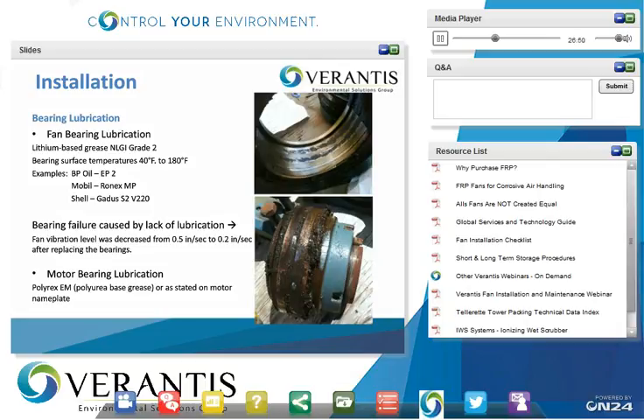Bearing failure caused by lack of lubrication. The arrow is pointing to the bearing housing and the bearing insert itself on the right. I was at a job site recently where the customer had complained of high vibration levels. It was tripping out on the monitor vibration sensors. And they had us come out and change the bearings. Well, when I disassembled the bearings, in the top picture, you can see the rust and the pitting inside the bearing housing itself. The lower photo shows the bearing, but there's also very minimal grease.